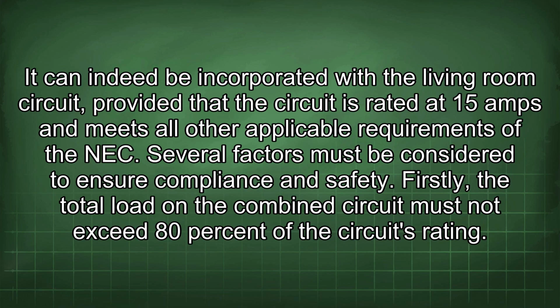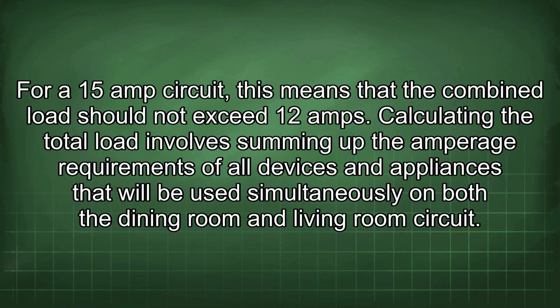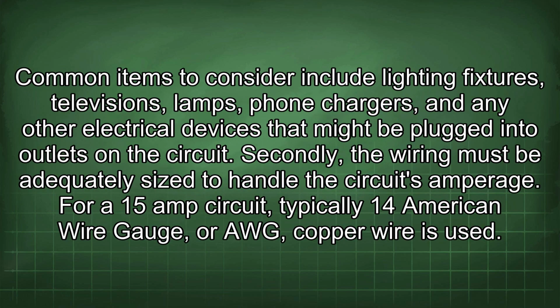Several factors must be considered to ensure compliance and safety. Firstly, the total load on the combined circuit must not exceed 80% of the circuit's rating. For a 15 amp circuit, this means that the combined load should not exceed 12 amps. Calculating the total load involves summing up the amperage requirements of all devices and appliances that will be used simultaneously on both the dining room and living room circuit. Common items to consider include lighting fixtures, televisions, lamps, phone chargers, and any other electrical devices that might be plugged into outlets on the circuit.